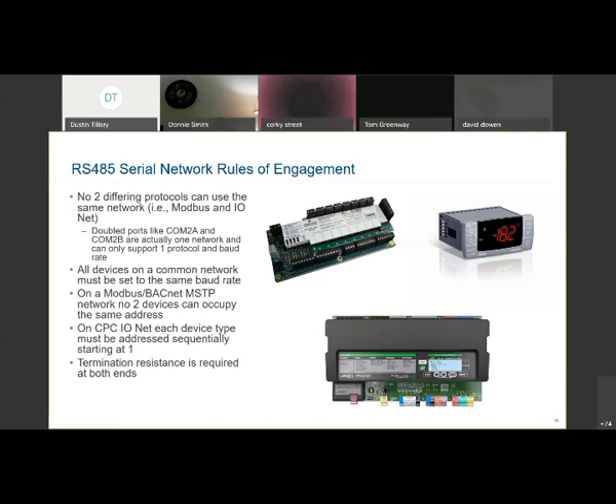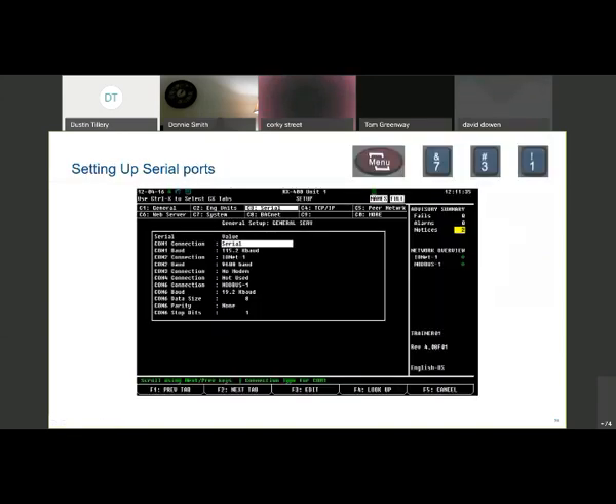And again, guys, termination. Termination resistance is required at both ends of the comm loop. I can't stress that enough. Terminate, terminate, terminate. Please terminate. All right. So once we have everything connected, now we need to go in and tell the E2 which COM ports are going to be what. To do so, you're going to use menu 731. It's going to take you to the serial tab. From here, you can specify what COM1 is used for, or COM2, as well as the baud rate of said device.